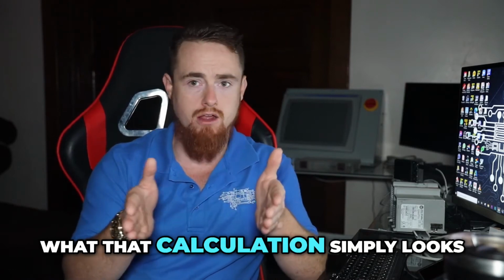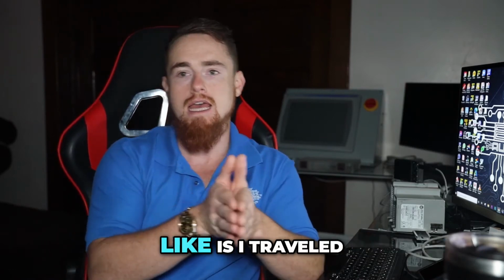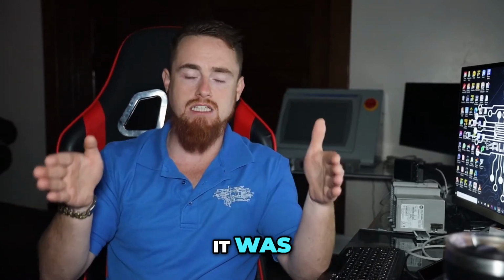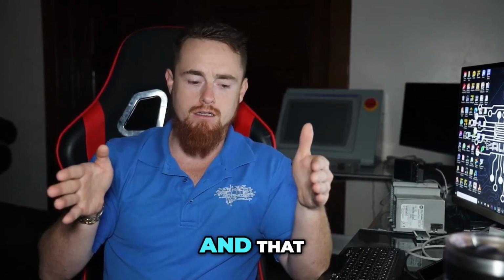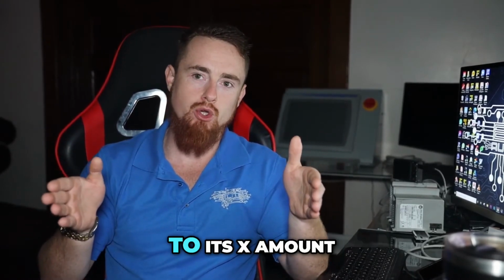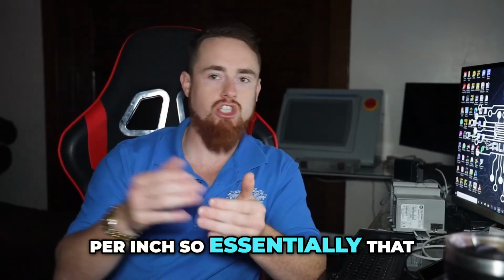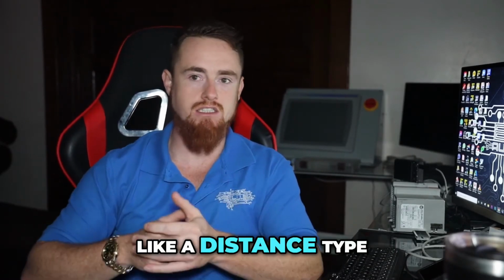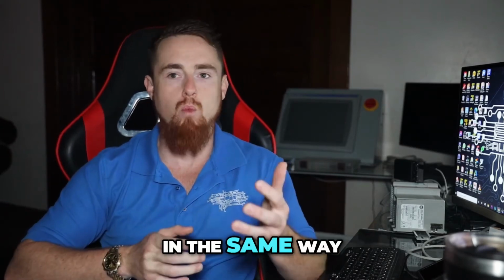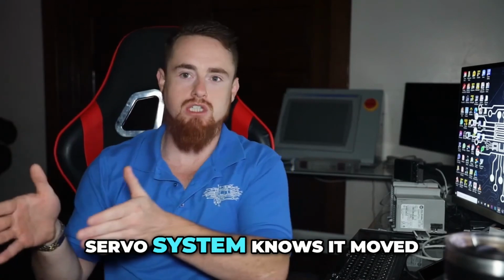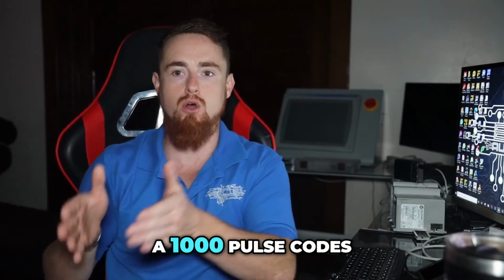So what that calculation simply looks like is I traveled X amount of distance and it was X amount of pulse codes. And that then builds a relationship to it's X amount of pulse codes per inch. So essentially that conversion is just made like a distance type of conversion, in the same way that we say it traveled 60 miles per hour. And so now that servo system knows it moved 1,000 pulse codes per inch.